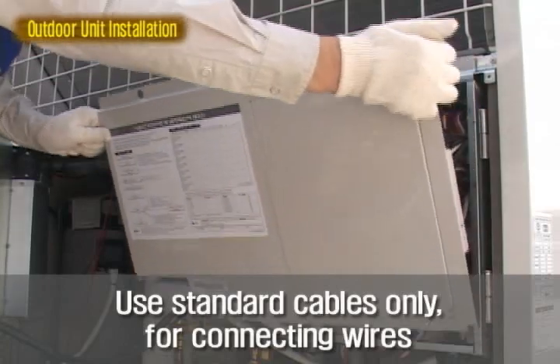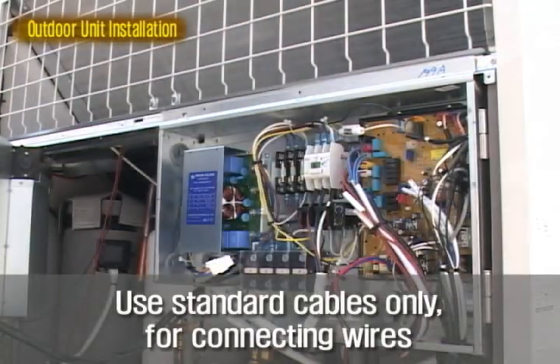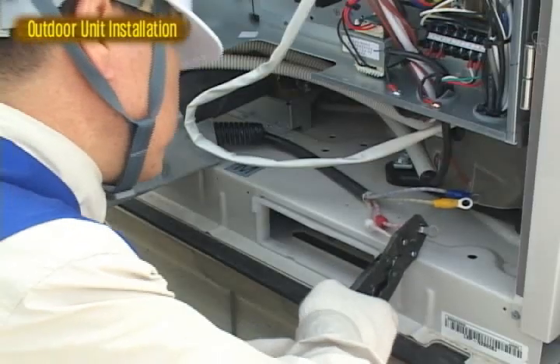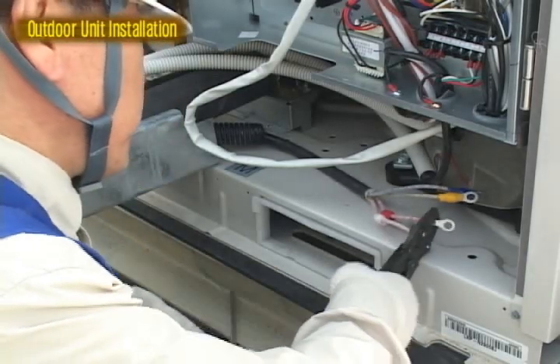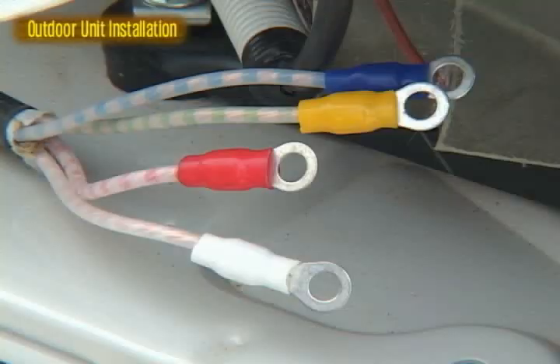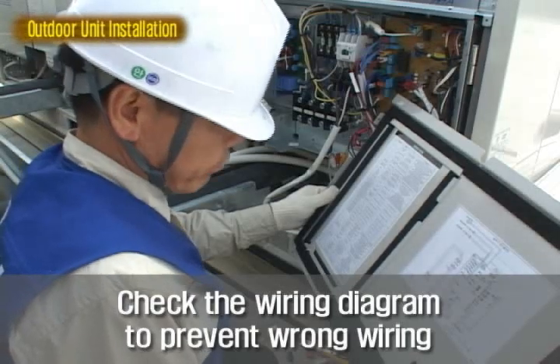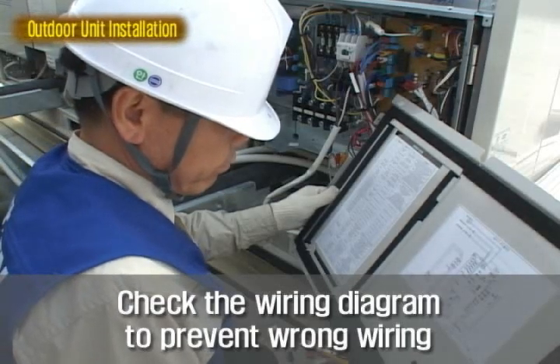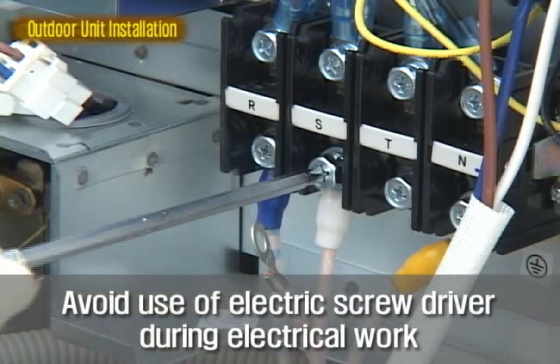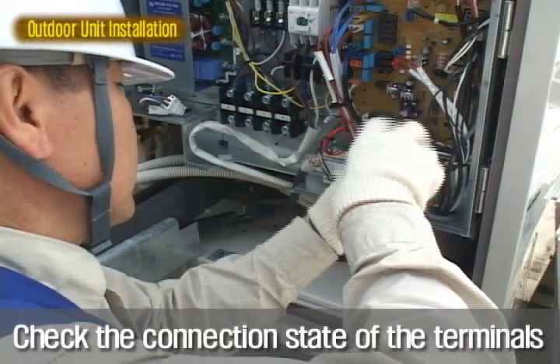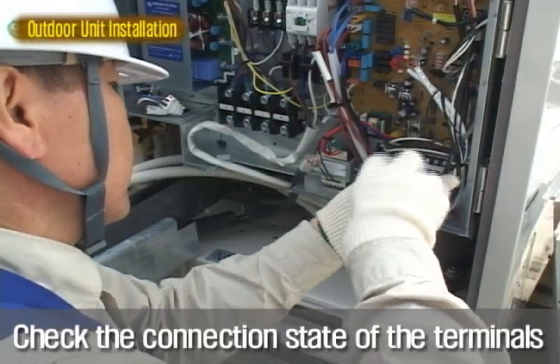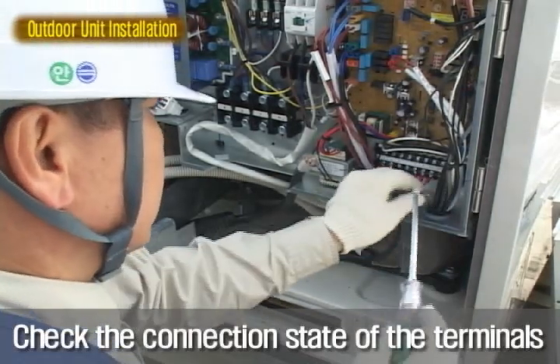Disassemble the control cover for cable connection. Terminal type connection is used to prevent contact resistance defects in the wire connection. Check the wiring diagram to prevent wrong wiring. Connect the power line to the outdoor unit and the transmission line between outdoor units and indoor unit by the diagram.